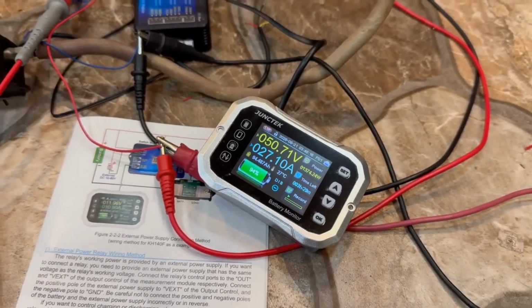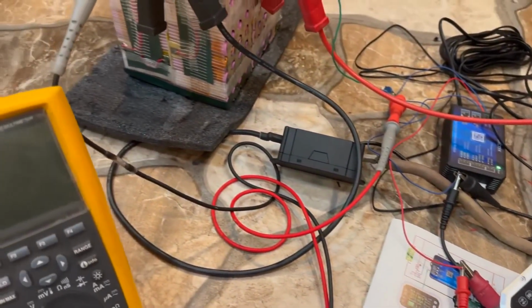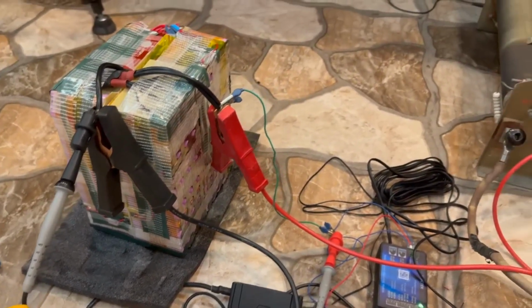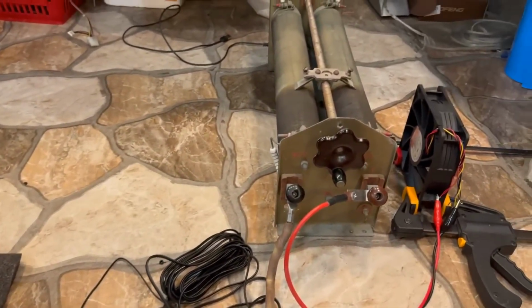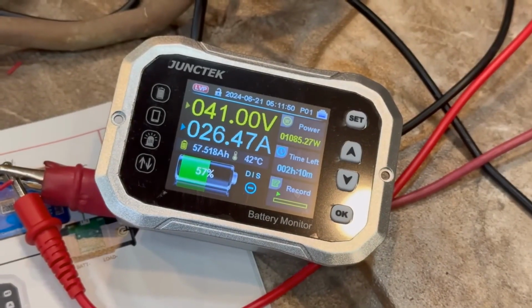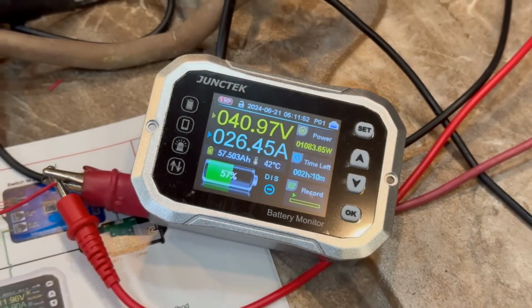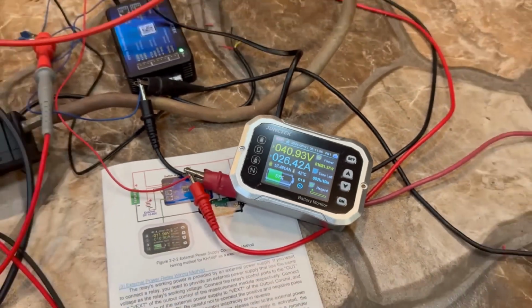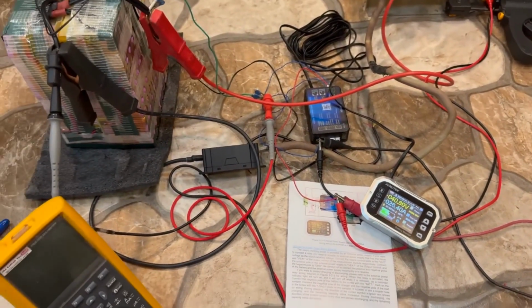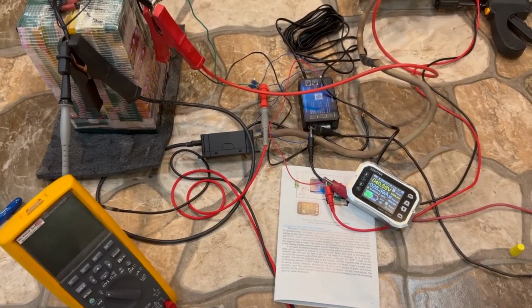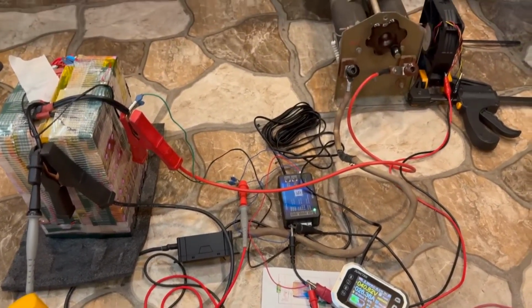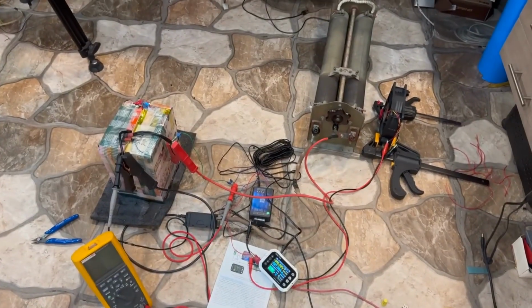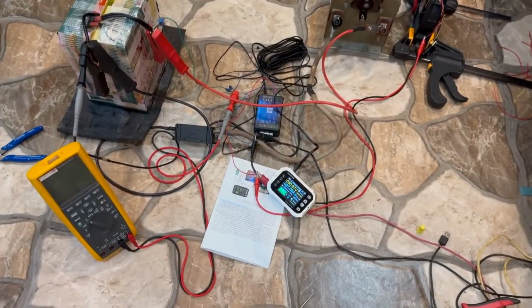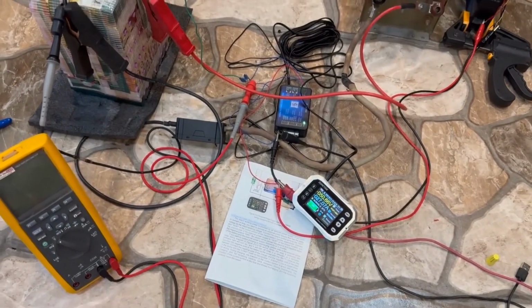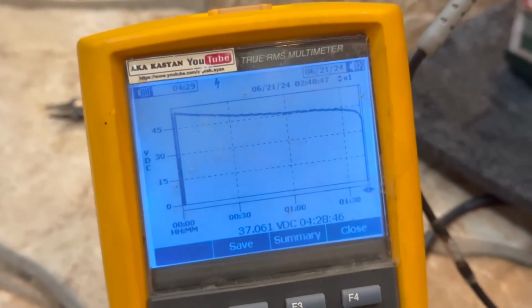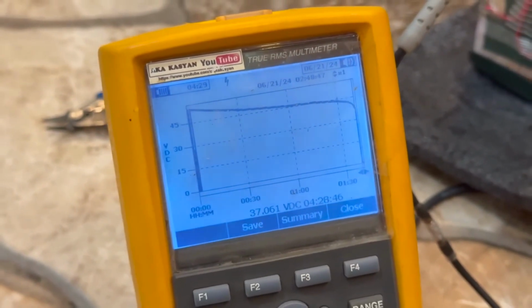On this monitor, I set the capacity to 100 amp hours. We discharged the battery until the BMS triggered at the lower voltage threshold. Next, we'll record the residual capacity on the monitor. Subtract the residual from the set 100 amp hours to get the actual capacity of our battery. The monitor's temperature sensor is attached to the BMS and shows its temperature. A multimeter data logger is connected in parallel to the battery, which monitors the battery voltage in recording mode. It will allow us to see the BMS trigger voltage at the lower threshold.